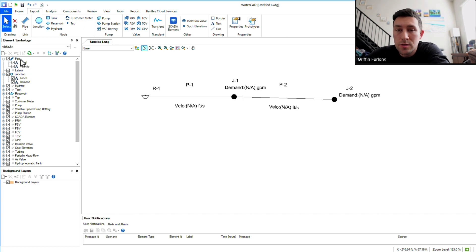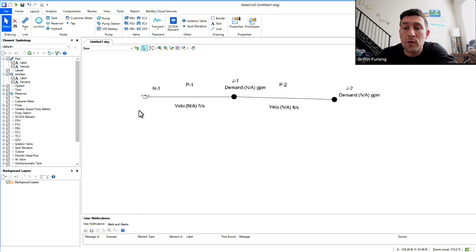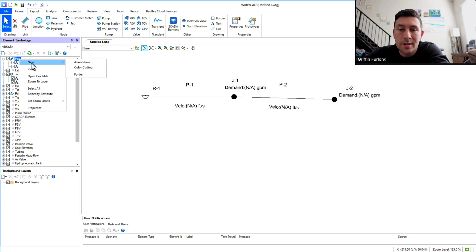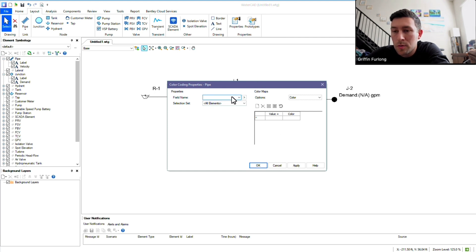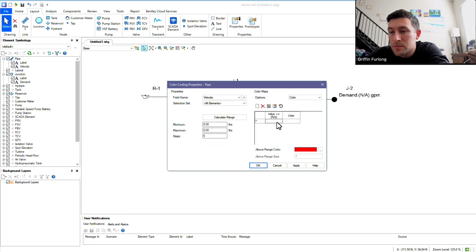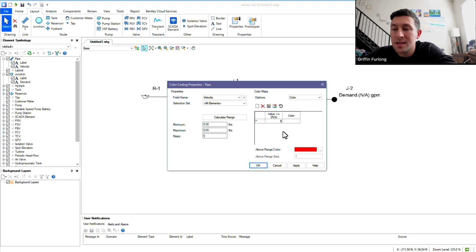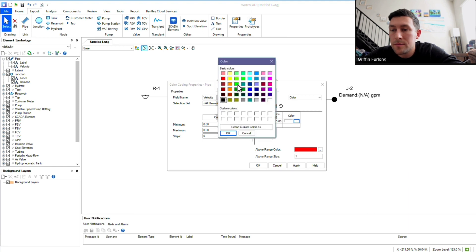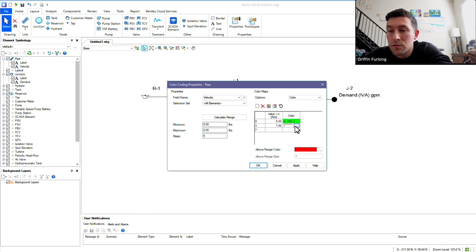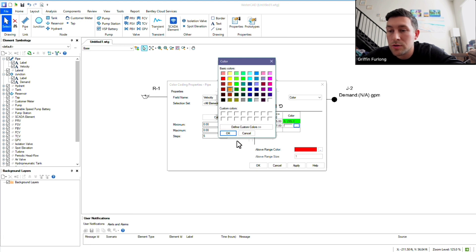Now let me show you how to do some color codes. Let's say you have a massive model and you're really just trying to create a nice exhibit to show where a pipe has a velocity over 5 FPS — how do you do that? Go over here to Pipe, Element Symbology, right-click New, and go to Color Coding. Here you have an assortment of field names. Let's go to the field name for velocity. Right now it's saying anything less than or equal to blank will be a certain color. So if I want to know what is less than or equal to 5 — I want to know if it's good — I'm going to say green is good. Anything above this will be red. If you want a range like maybe 7 FPS, you can also create that as a different color. Then hit Apply.